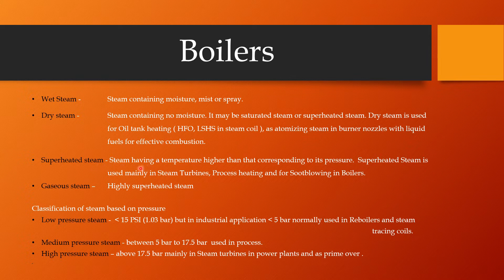Superheated steam is steam having a temperature higher than the corresponding temperature to its pressure. Superheated steam is used mainly in steam turbines in power plants or as a prime mover in industrial applications. Also in process heating and for soot blowing in the boiler. Soot blowing is normally done in each and every shift to remove the soot, and for that we have to use only superheated steam.